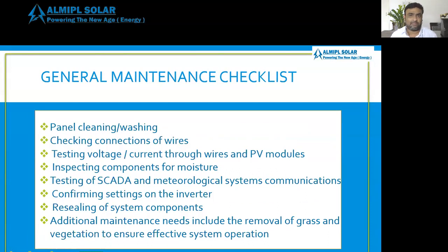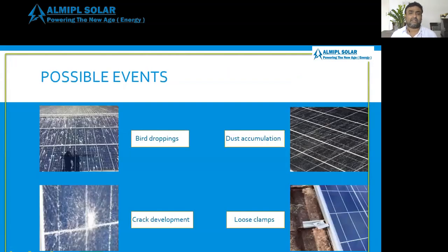General maintenance checkup. So every month or 15 days once, we need to check up: general panel cleaning and washing, checking connections of wires, testing voltage and current through wires and PV modules, inspecting components for moisture, testing of SCADA and meteorological system communication, confirming settings on the inverter, resealing of system components, and additional maintenance needs including the removal of grass and vegetation to ensure effective system operation.